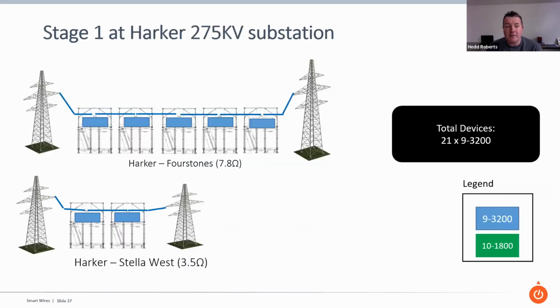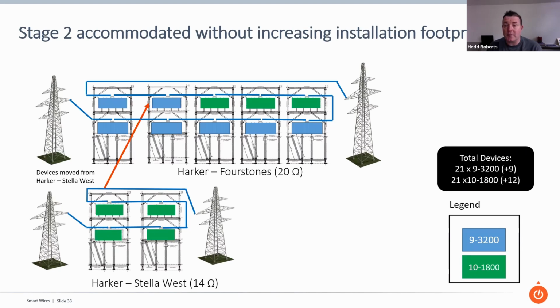This is a representation of one of those sites, Harker, where you can see 5 devices per phase in the Harker to Fourstones circuit, and 2 devices per phase in the Harker to Stella West circuit - that was the original stage 1 installation. In the extension project, the amount of devices was doubled, from 5 to 10 in the Harker Fourstones circuit and 2 to 4 in the Harker Stella West circuit. Importantly, by double stacking the devices this way, we achieved that extension with no increase to the footprint of the initial deployment.